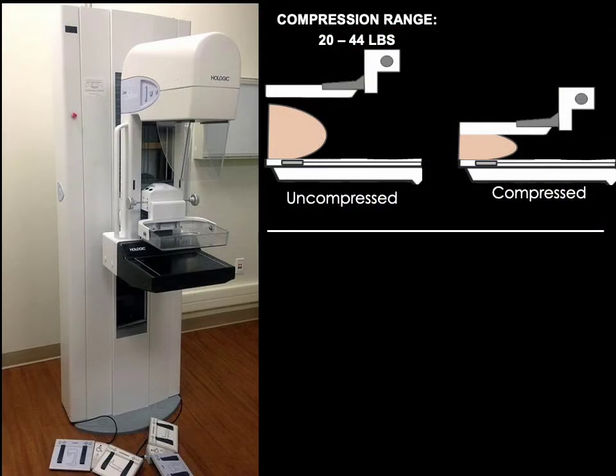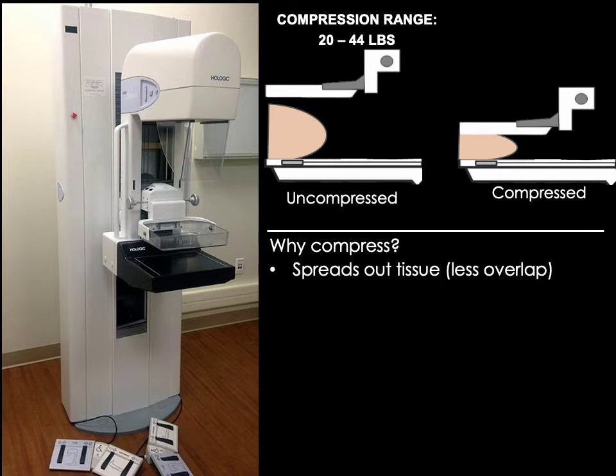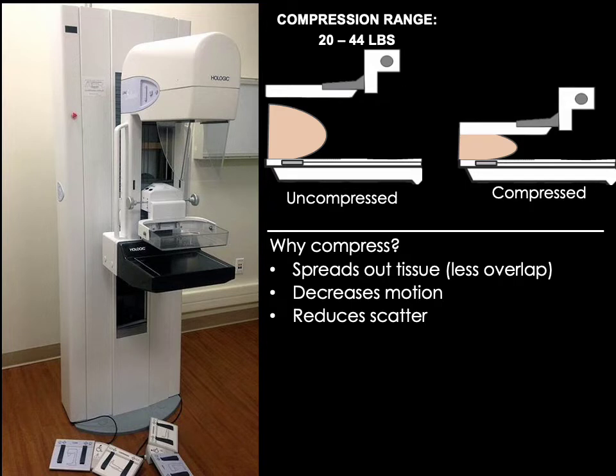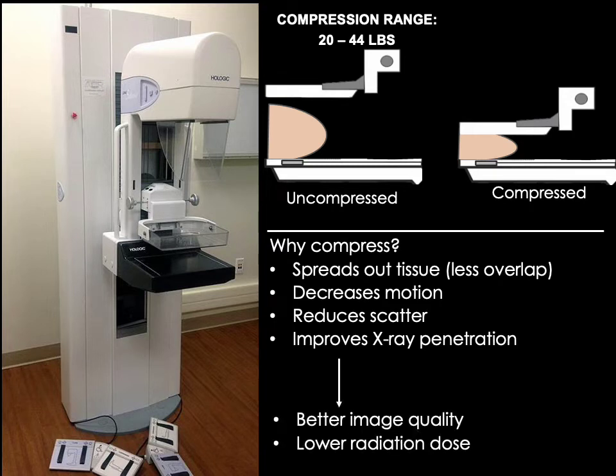Now let's talk about the compression paddle and why compression is so important in mammography. First, compressing the breast spreads out the breast tissue so there's less overlap, improving visibility of structures within the breast. Second, compression helps to decrease motion because the breast is immobilized. Third, by compressing the breast tissue, we decrease the thickness of tissues that x-rays pass through, which reduces scatter and improves x-ray penetration. This gives us better image quality and decreases dose.